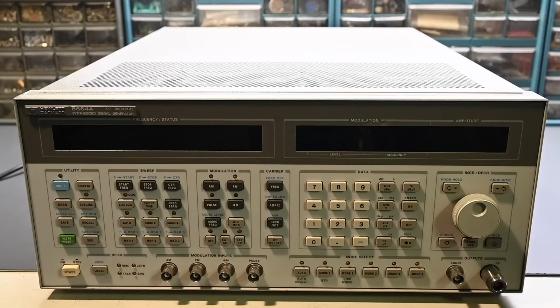Essentially, it can completely calibrate itself. There are a few internal adjustments that you would have to make for a complete calibration, but the normal calibration routine is all done in software, and essentially the instrument can just sit there, calibrate itself, and you're ready to go. The built-in self-tests are very complex and very extensive, and it can isolate the problem down to individual modules or a defective cable, power supply issues, and so forth. So again, very extensive built-in capabilities.